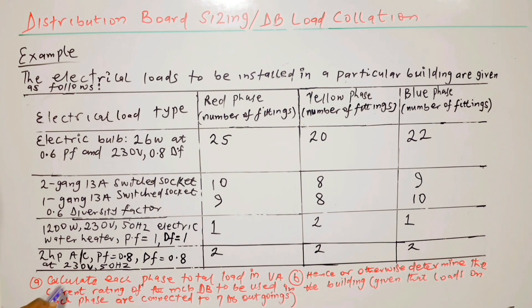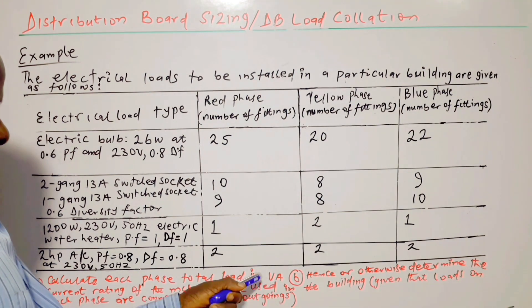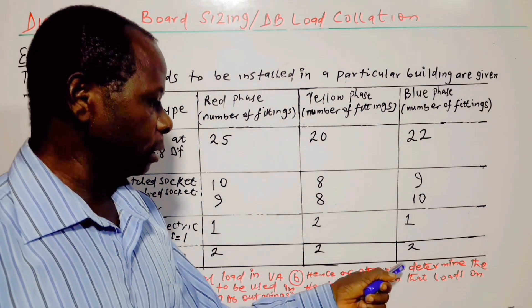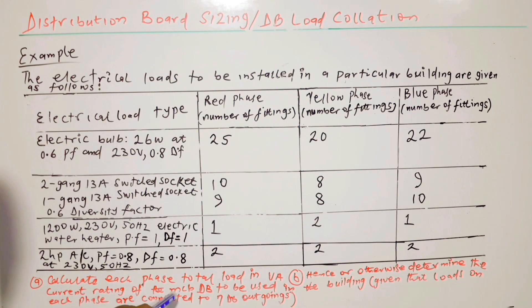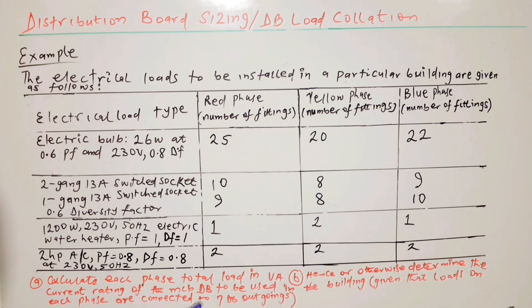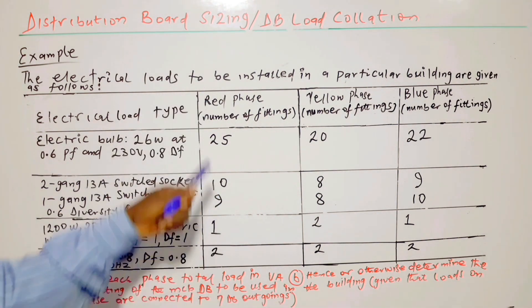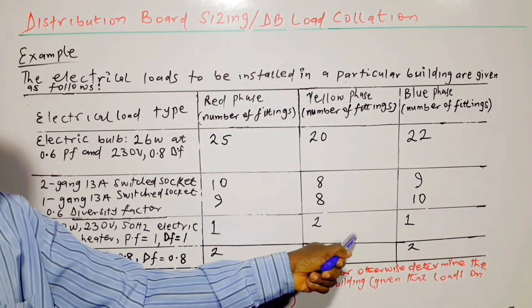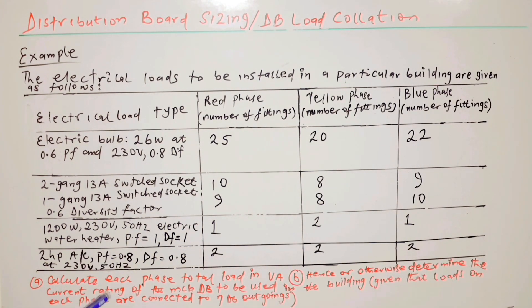Now the questions. Part A: calculate each phase total load in VA — that is the apparent power S on each phase. Part B, hence or otherwise, determine the current rating of the miniature circuit breaker distribution board to be used in the building, given that loads on each phase are connected to 7 DB outgoings. That means 7 for red, 7 for yellow, 7 for blue — giving a total of 21 — because it's a 3-phase distribution board.